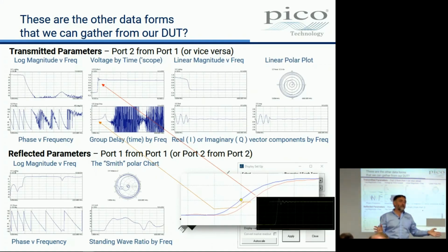And lots of you here have heard us talk a lot about, can we have S parameter analysis on the 9311, i.e. convert from the time domain? Yes, it's all possible, right? But we don't have it. Here it is. This has the transformation embedded within the Vector Network Analyzer. Okay, so what's that? That's 8 plots. We've got 8 plots, all of the same data that are useful in different ways in analyzing networks.